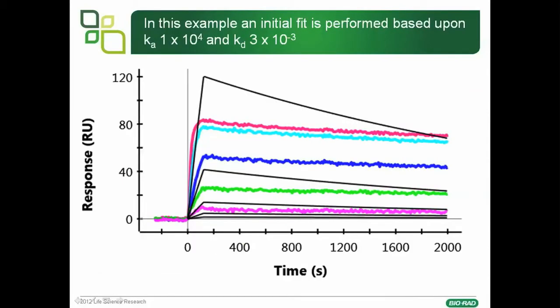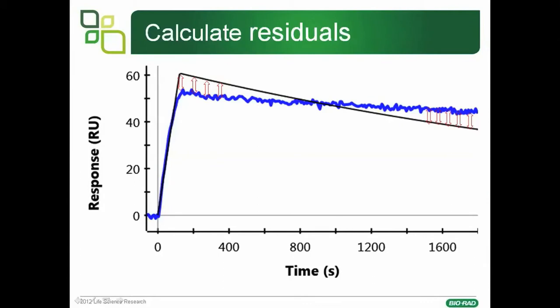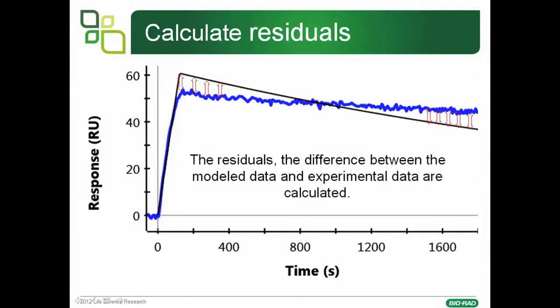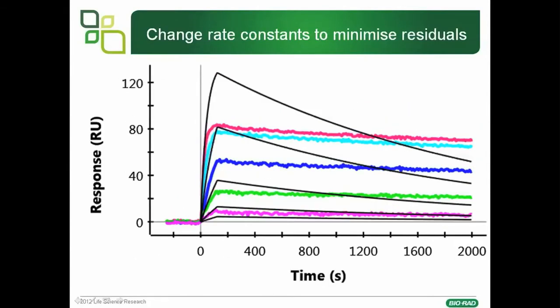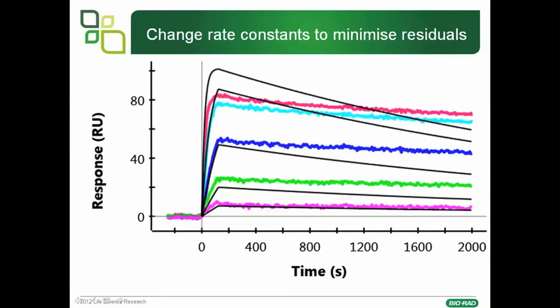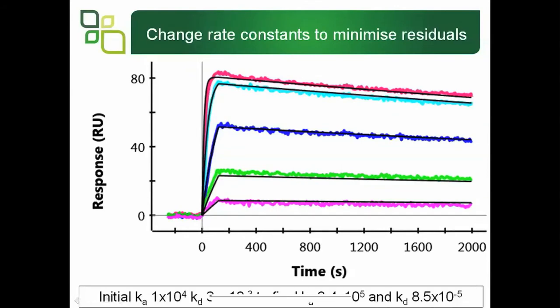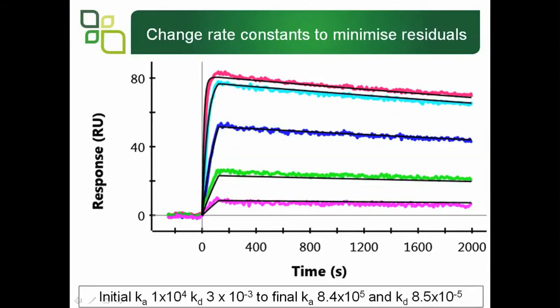What the software does is change the rate constants based on the residuals. For the initial rate constants, it looks at the residuals — the difference between the experimental data, the blue line, and the fit data, the black line. The residuals are calculated, and the software then changes Ka and Kd values to decrease the residuals and generate rate constants closer to the experimental data. The software goes through many iterations to minimize residuals and generate rate constants that match the experimental data as closely as possible.